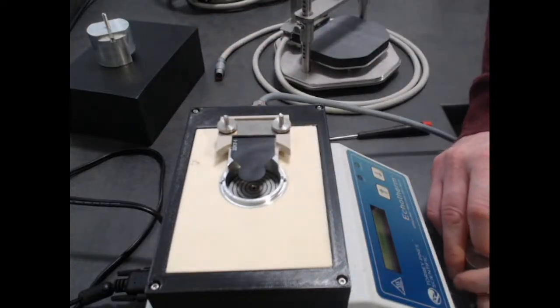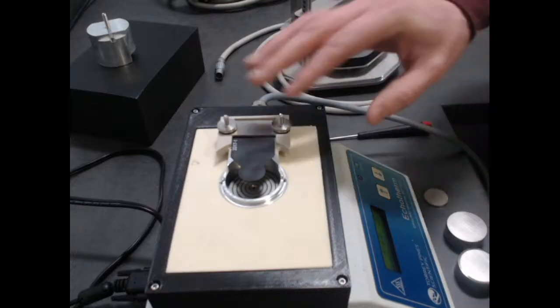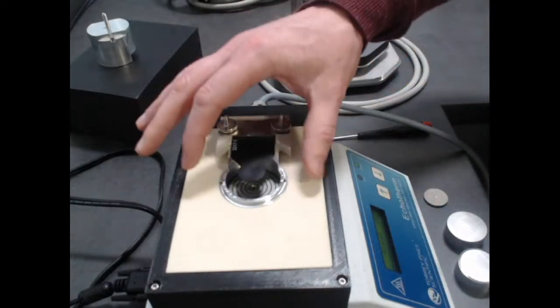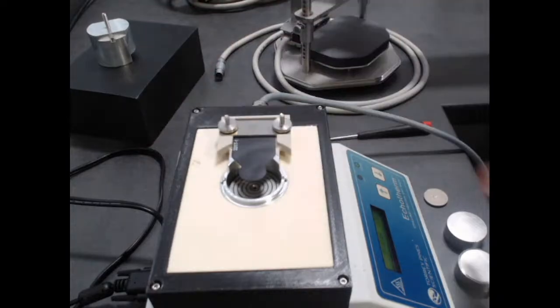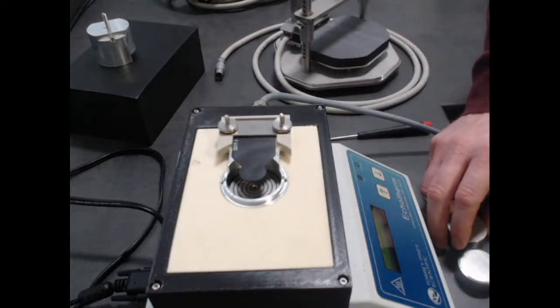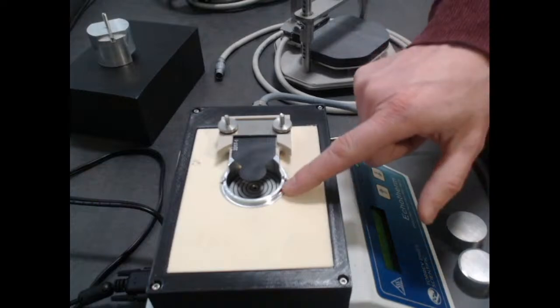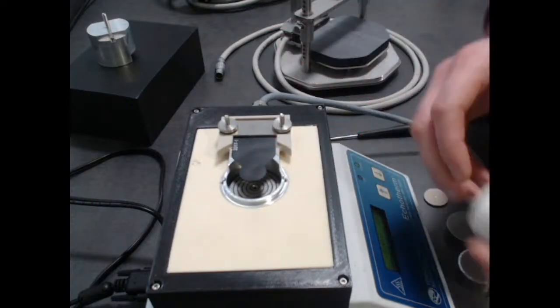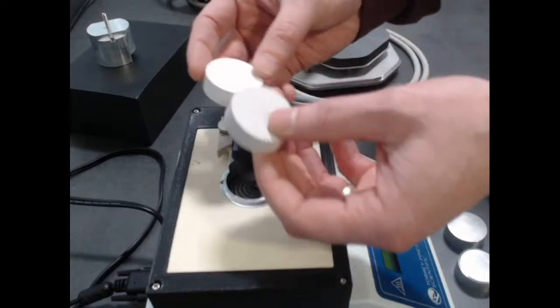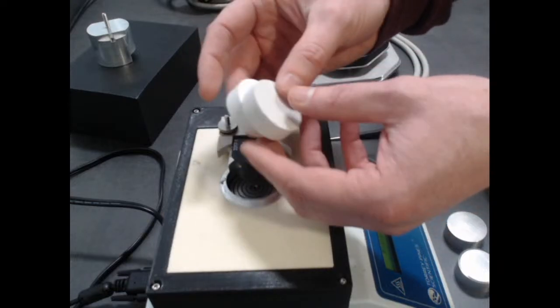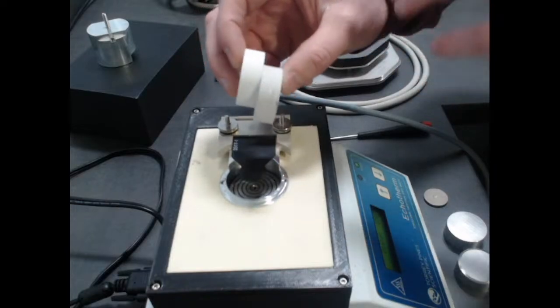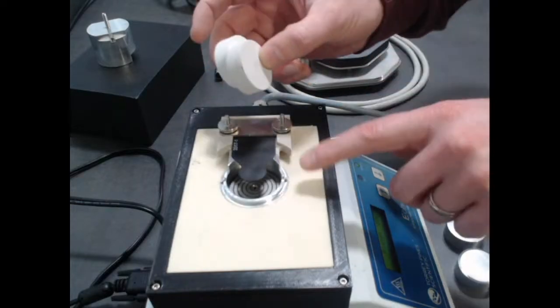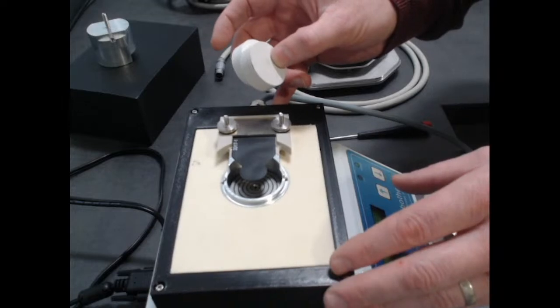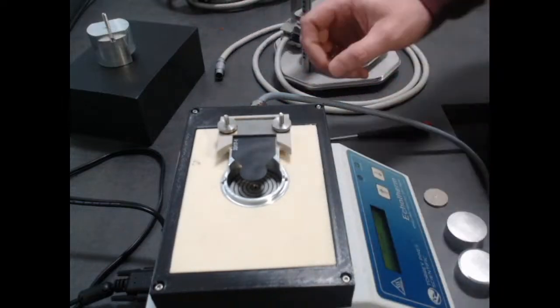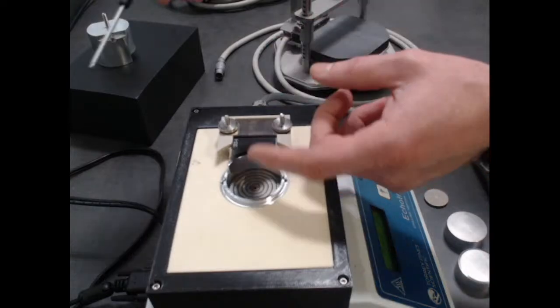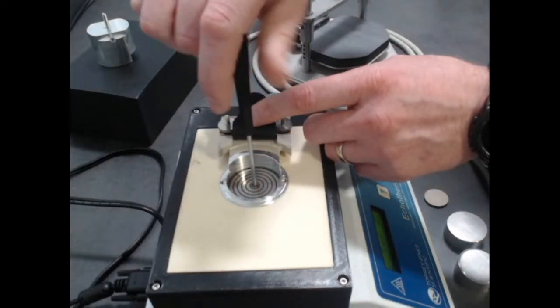And then if we were going to do an asymmetric setup, you can do an asymmetric setup in this physical setup and on any other device we have by including insulation. So the sandwich would be insulation, sensor, sample. In this case, if you buy a high temperature device, you get two pieces of calcium silicate, whose temperature range is up to several hundred degrees. So it's certainly more than we need for this simple temperature option that goes up to 100 degrees. The floor of this goes up and down to account for different sample heights.